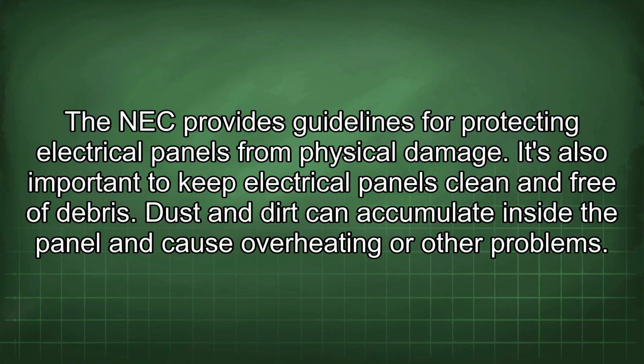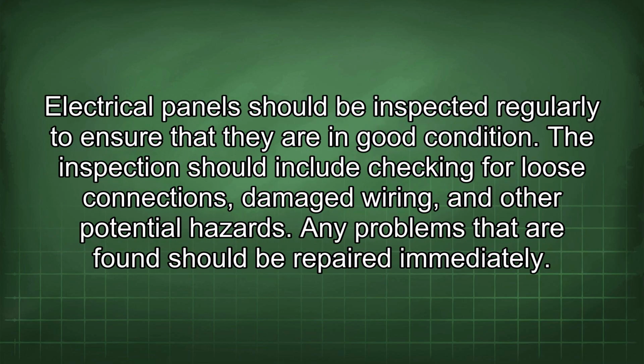It's also important to keep electrical panels clean and free of debris. Dust and dirt can accumulate inside the panel and cause overheating or other problems. Electrical panels should be inspected regularly to ensure that they are in good condition. The inspection should include checking for loose connections, damaged wiring, and other potential hazards. Any problems that are found should be repaired immediately.